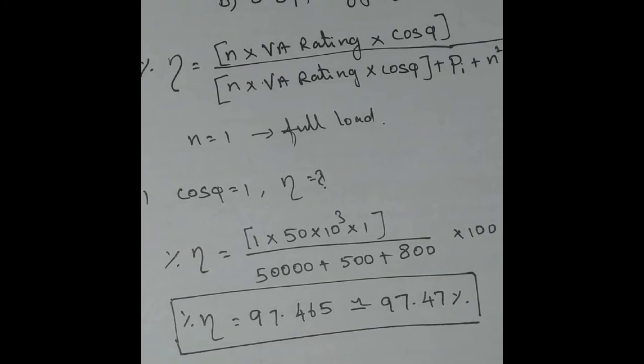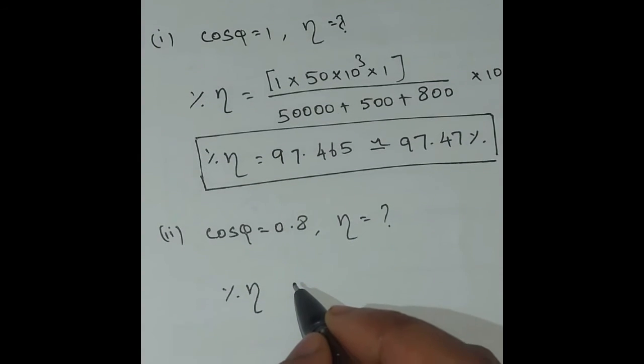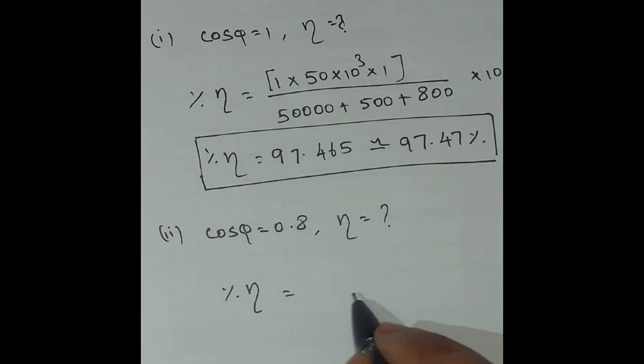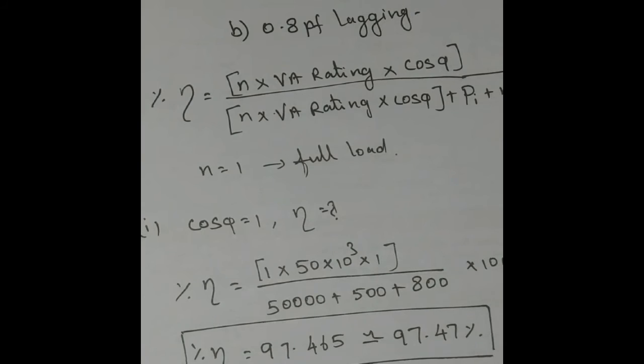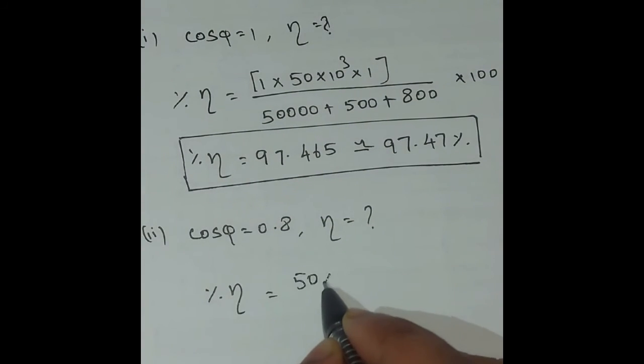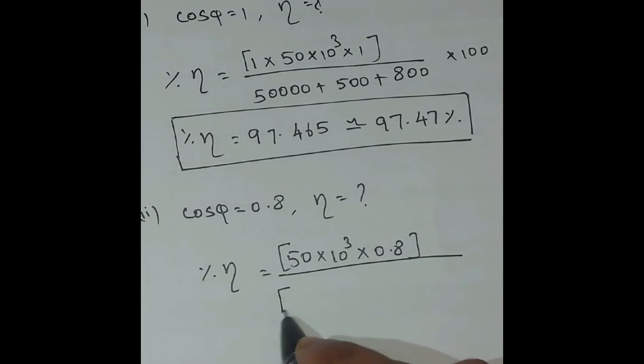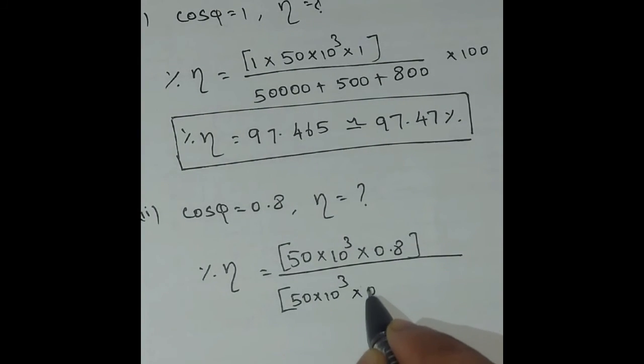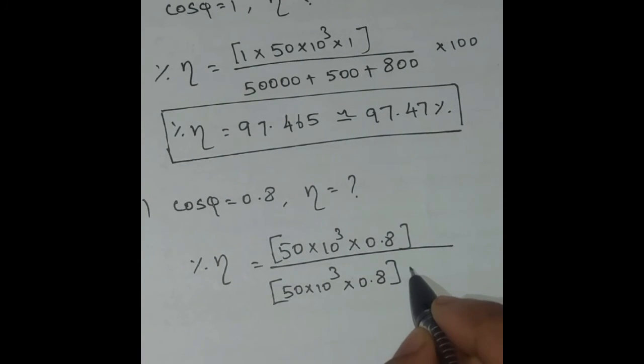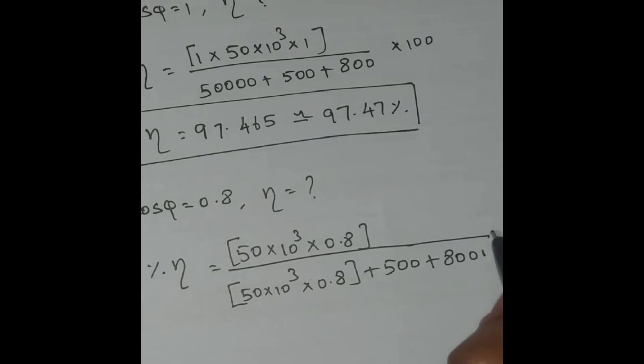For Case 2, cos φ equals 0.8. The percentage efficiency formula is: n × VA rating × cos φ, divided by n × VA rating × cos φ plus losses. Substituting: 50,000 × 0.8, divided by 50,000 × 0.8 plus iron loss 500 watt plus full load copper loss 800 watt, multiplied by 100.